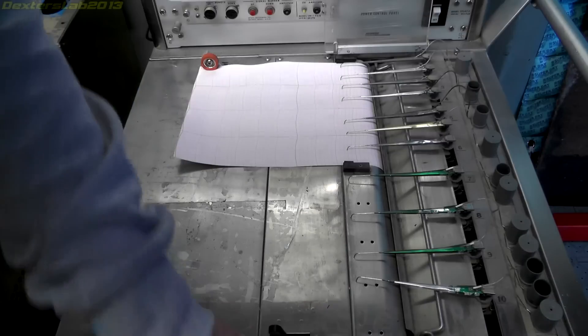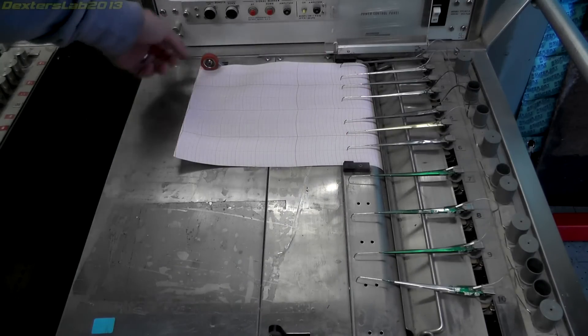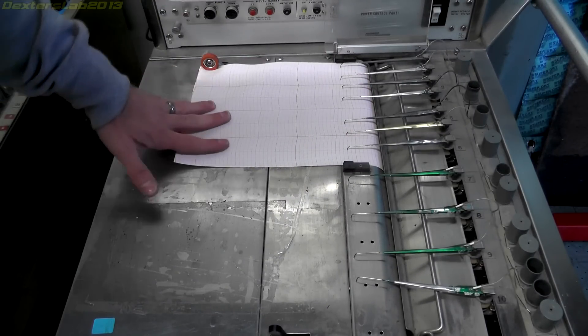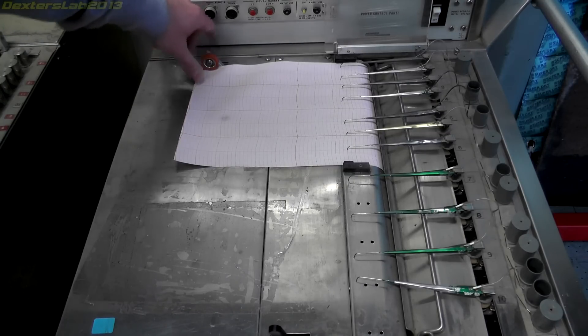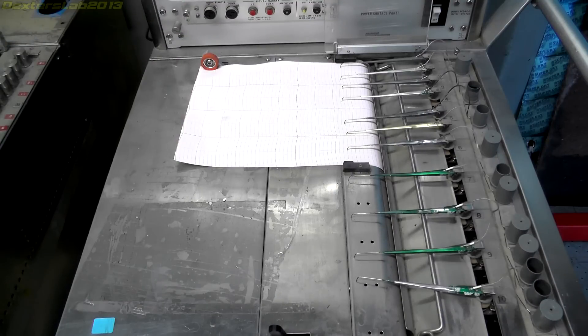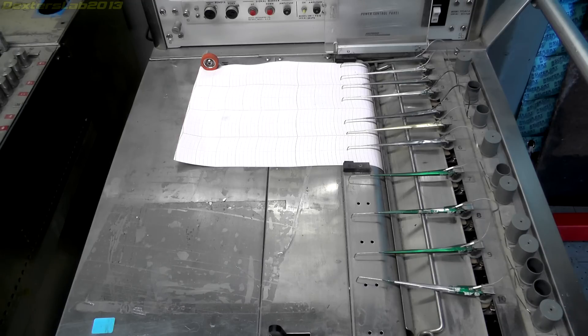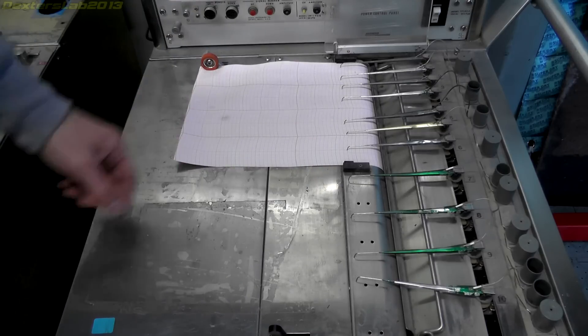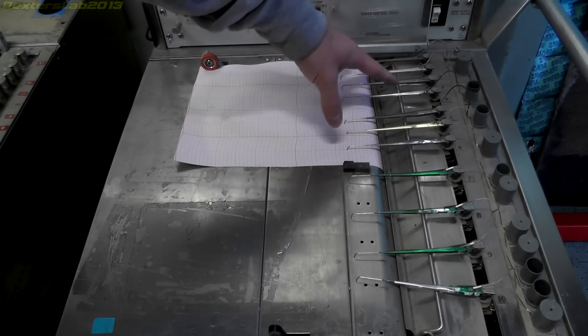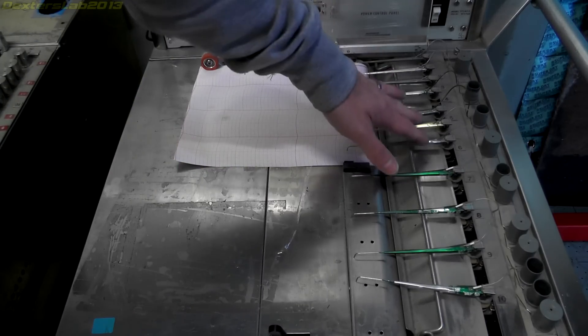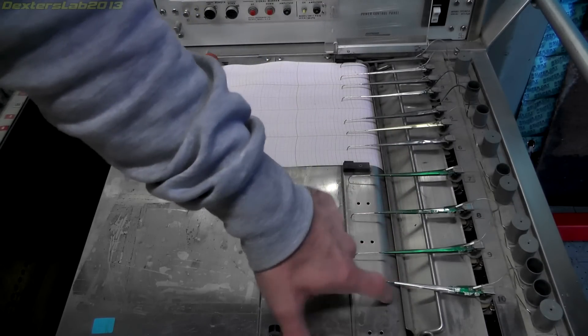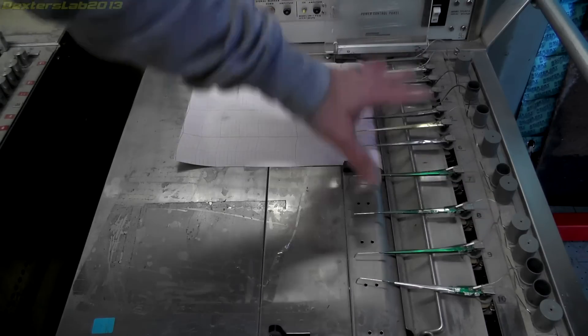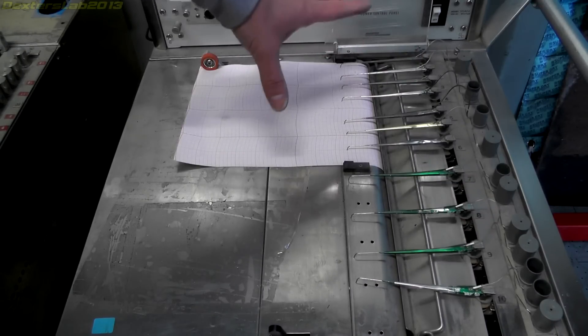Now obviously the paper is fed up through the bottom, comes through this section here, and it's actually pulled along the base by this little motor drive thing here. It's variable speed. You can change the speed between 1.5 millimetres per minute, which is really slow, all the way up to 60 millimetres a second. So that would be moving fairly quickly. As I mentioned earlier, for each of these pens there's a driver amplifier. But you can probably already see that there's 10 pens installed on this machine. Why there is more pens than you have driver amplifiers I'm not entirely sure.